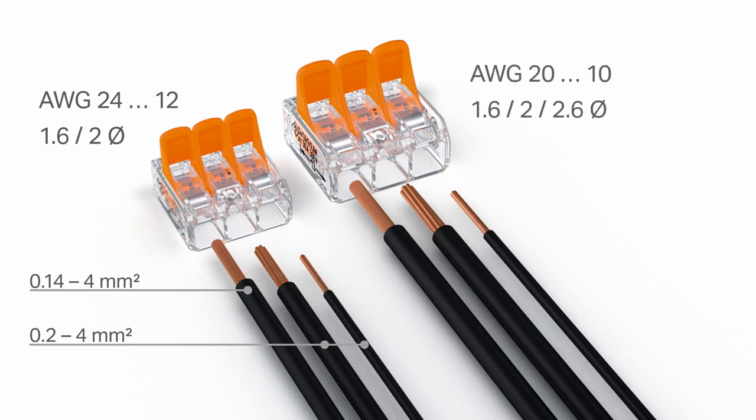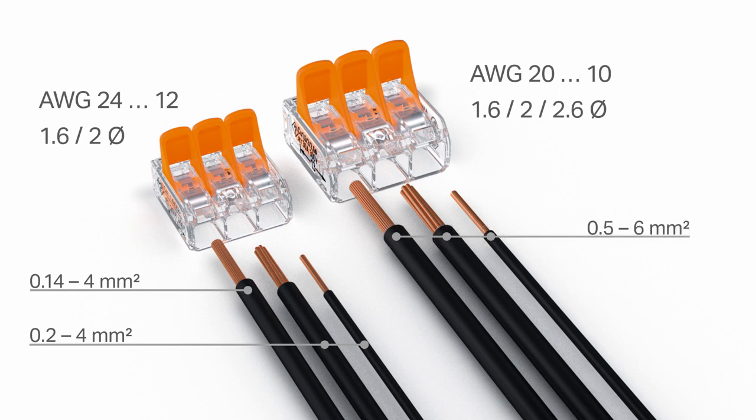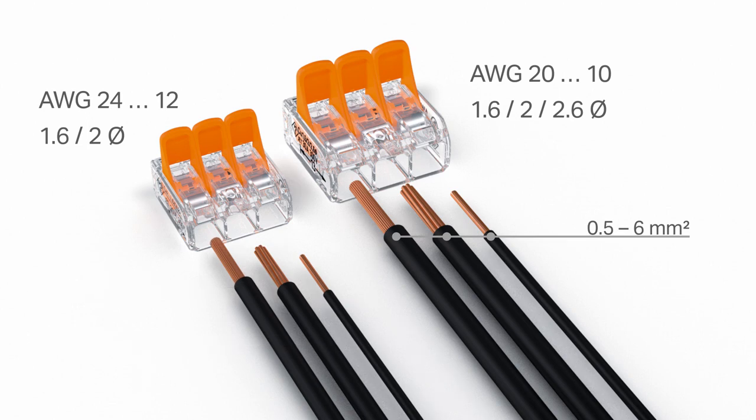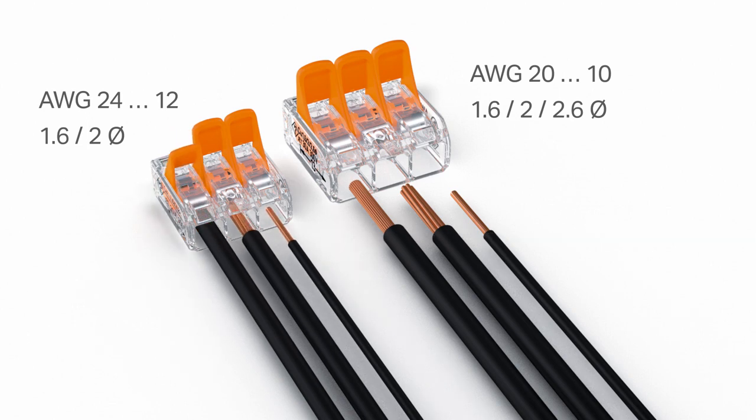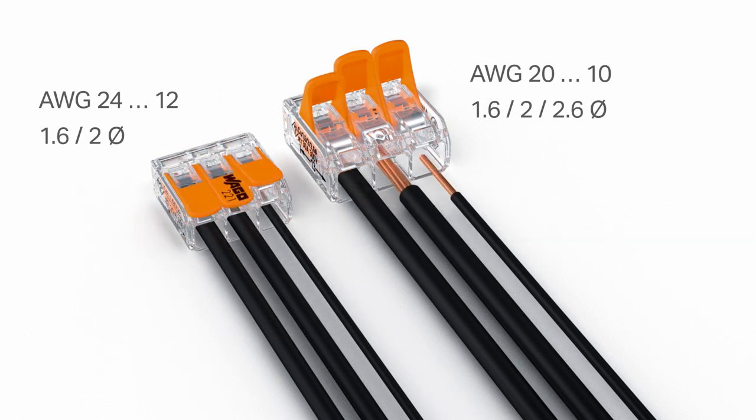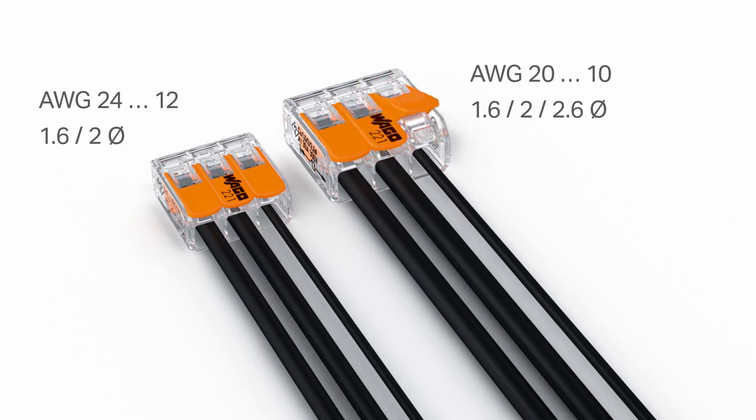The 6 square millimetre 41 amp version connects all conductor types ranging from 0.5 to 6 square millimetre. This flexibility permits a wide range of applications, especially when conductors of different types and sizes are used together.